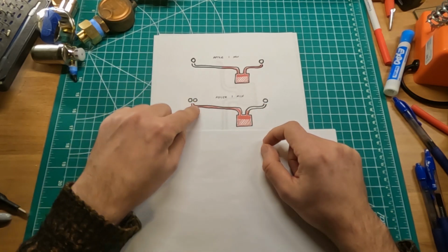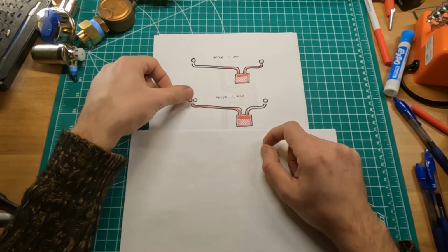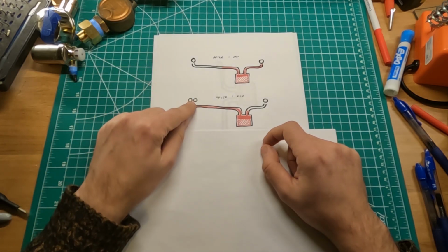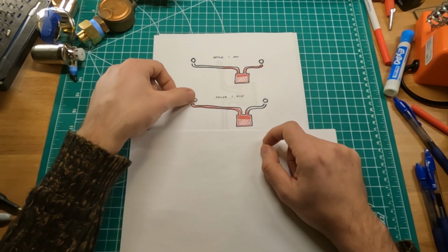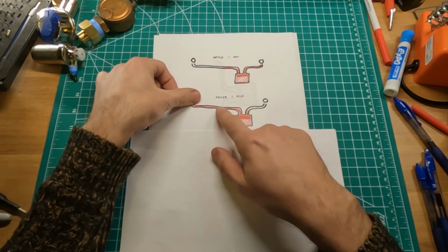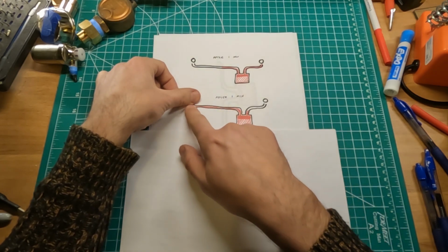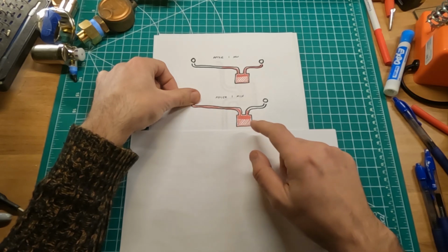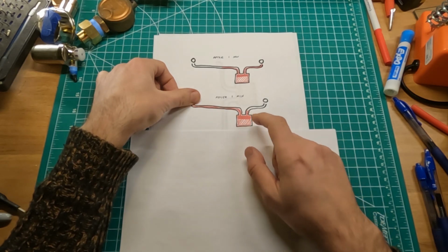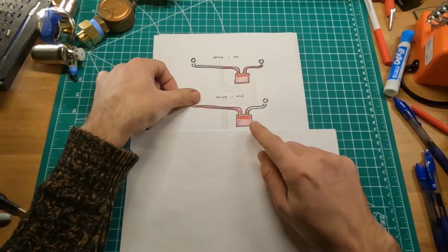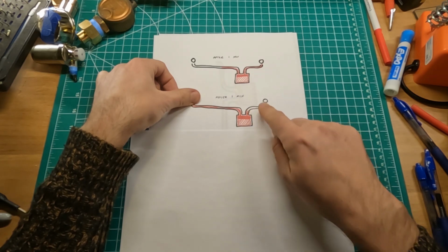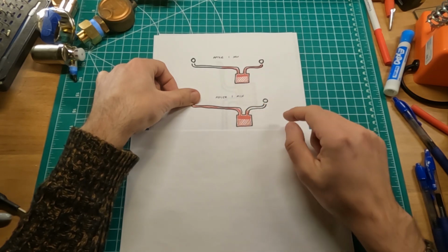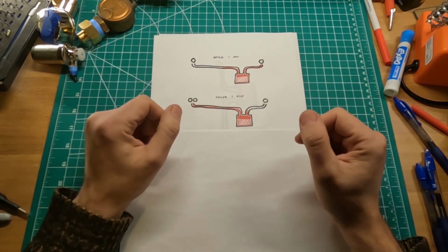Now of course then at some point the steam hits those valves, and they end up being closed, so because of that the steam cannot keep on pushing through this main pipe, and the boiler keeps on producing steam. So all of a sudden that steam has no other way than to go in this direction, and that's when that main starts filling up. So let's see what would happen.